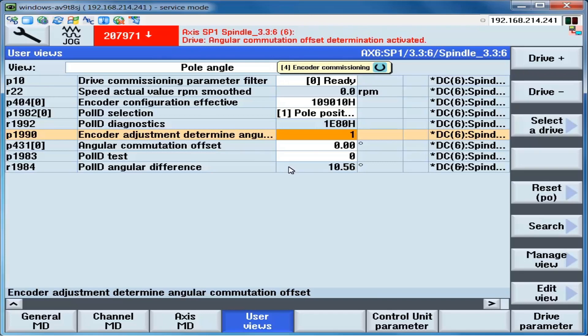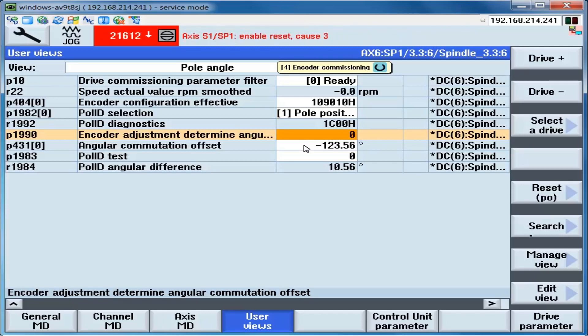And now we must jog the axis until we reach the reference mark. When the reference mark is seen by the drive, parameter P1990 will automatically set back to 0. And a pole angle will appear in P431. We're going to slowly jog the motor. And now P1990 has been set to a 0. P431 has a pole angle.